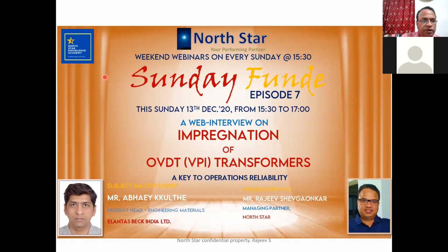Another question is, what is the useful life of a transformer? Normally it depends. As I said, there are three factors on which the transformer life depends: the build factor, the service condition, and the inherent factors. The build factors and inherent factors are, up to some extent, dependent upon the transformer manufacturer and at what level the transformer is made. Service condition is definitely in the hand of the user. As a cumulative effect of all these three factors, if everything is right, a transformer normally should serve you 25 to 30 years. If it is maintained nicely, it can easily go to around 30, 35, even 40 years.